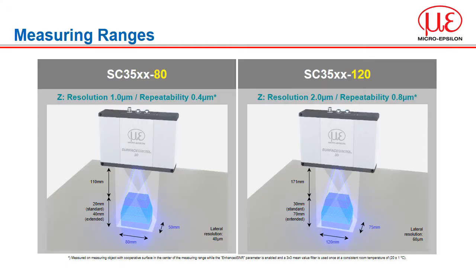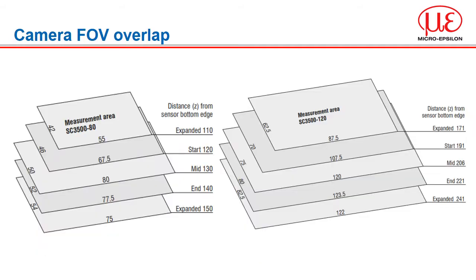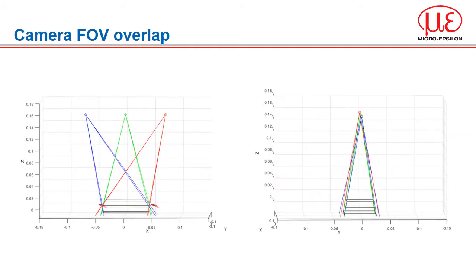Two sensor ranges will be offered at first: the dash-80 and the dash-120 model. The numbers refer to the width of the area at the mid part of the measurement range. Because we have two cameras viewing the same area, the field of view we can measure is shaped by how the cameras overlap. On the dash-80 model, the X field width reduces from 80mm down to 75mm, whereas the longer range dash-120 reduces down to 122mm at the end of range. The reason for this is the alignment of the two cameras and projector.